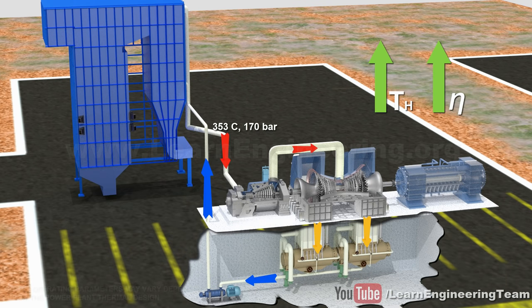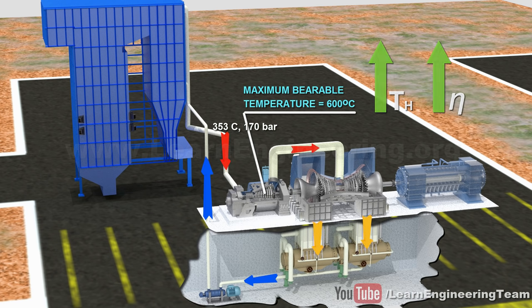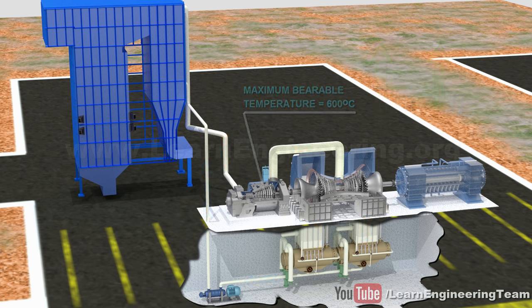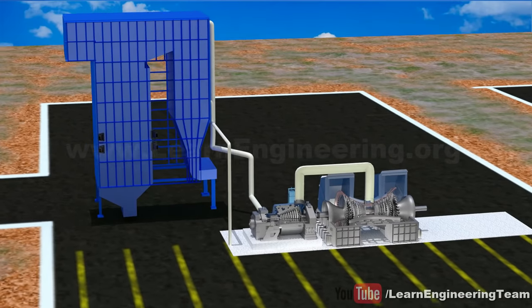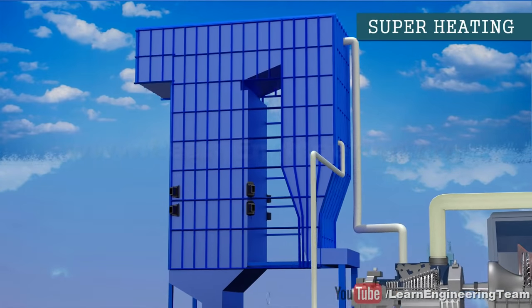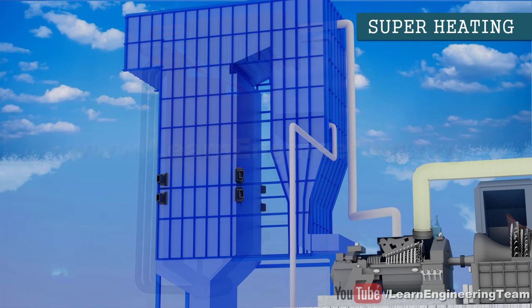The steam turbine blade material cannot withstand temperatures greater than 600 degrees Celsius. So, one more heat exchanger is added after the steam drum to superheat the steam and it is heated to the maximum allowable limit.